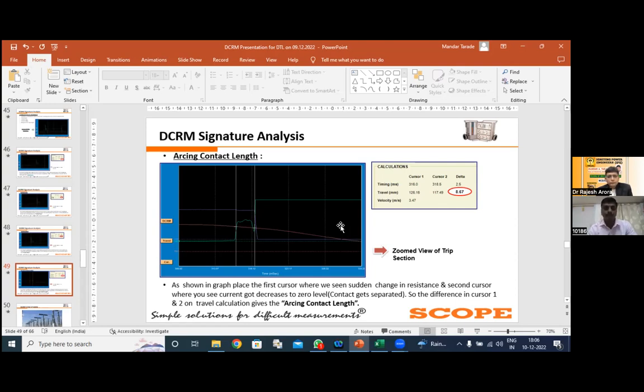Next point is the arcing contact tip length. I already told you that the contact tip is coated with, or made up of, tungsten alloy or chromium alloy, which has a high temperature coefficient. Whenever you are calculating the arcing contact tip length, first keep the first cursor at the sudden change in the resistance point, and the second cursor where your current goes down to zero. The delta between these two points is the arcing contact tip length. Why? Because at the time of release, your main contact releases first, and then your arcing contacts release. So with the help of this DCRM signature, you get an idea about the contact travel, contact gap, contact wipe and arcing contact tip length.